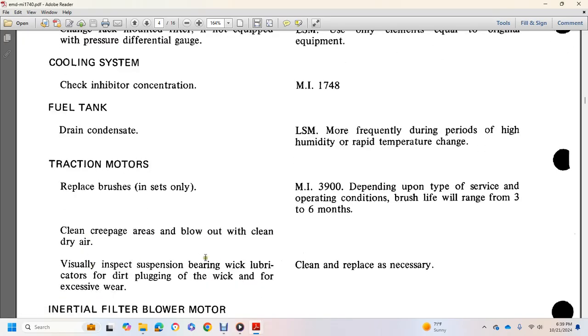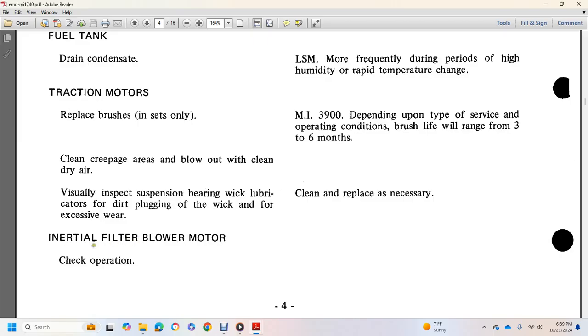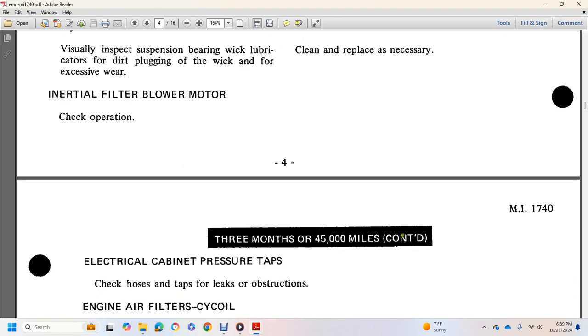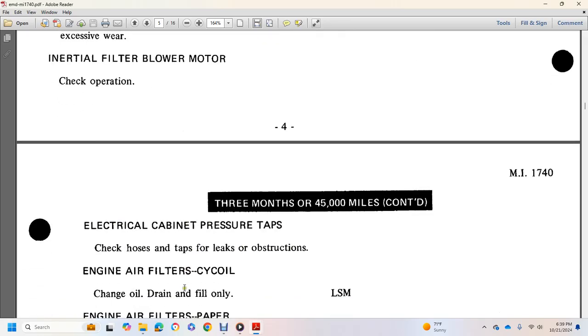Visually inspect the suspension bearing wick lubricators for dirt plugging on the wick and for excessive wear. Check and clean and replace as necessary. Inertial filter blower motor: check the operation. Continued, electrical cabinet pressure taps. Check hoses and taps for leaks and obstruction.